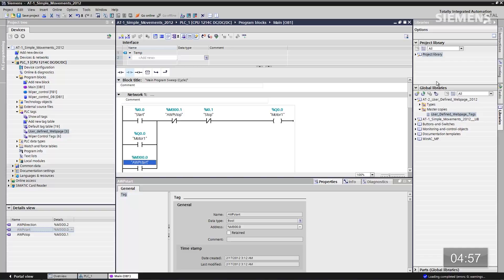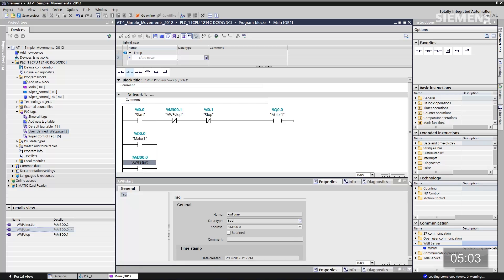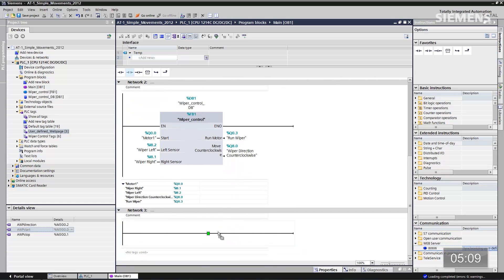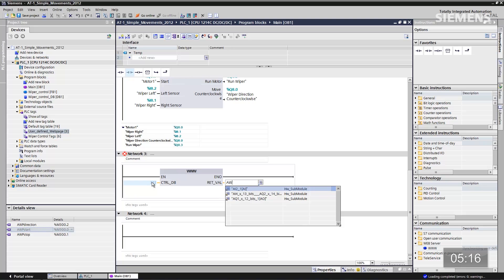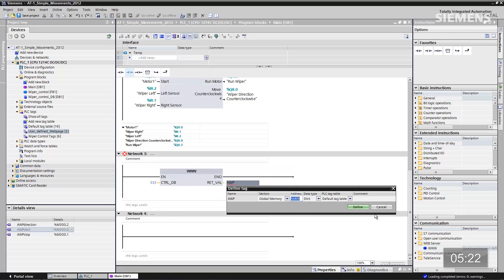All I have to do is tie them together — there's the stop, there's the start. Now our virtual logic and actual logic are tied together. The next step is to add a WWW block, because this is a user-defined web page and we want to call the virtual logic against the actual logic in the CPU. Go to instructions, web server, and add this block. The control data block is always 333, and for the output I'm typing in a tag name 'AWP' using the default — that's fine.